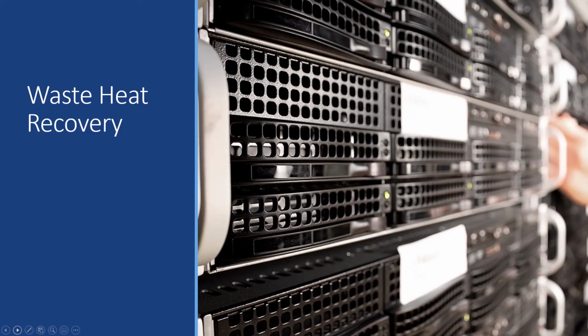I was able to walk through a small business who were able to recover the heat generated from their server room to use as supplemental heat within their building. This allowed them to turn on their primary heat much later in the year and then turn it off much sooner in the year. The server room was located in the basement, and through an exhaust fan, the heat was pushed from the basement into the office area. This practice allowed the small business to reduce their heating costs by 38%.